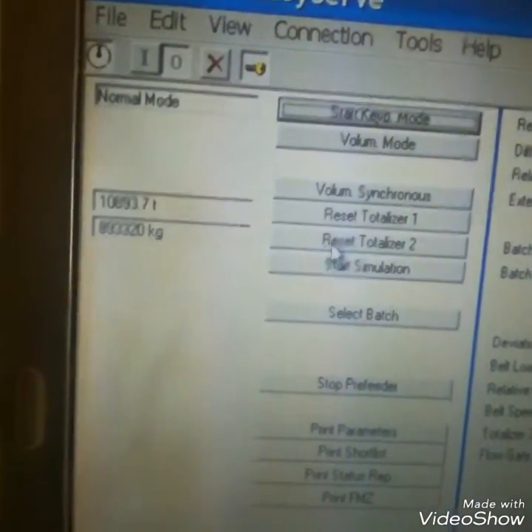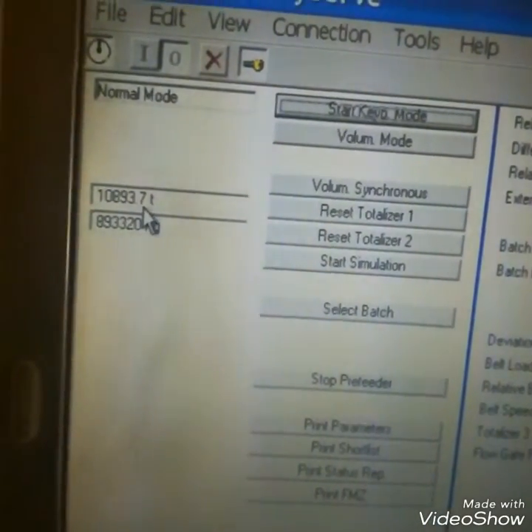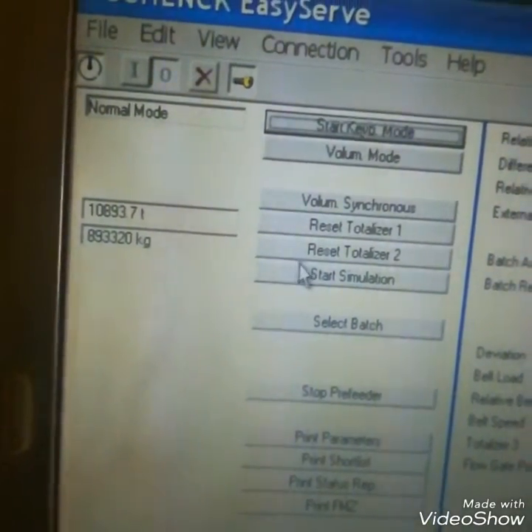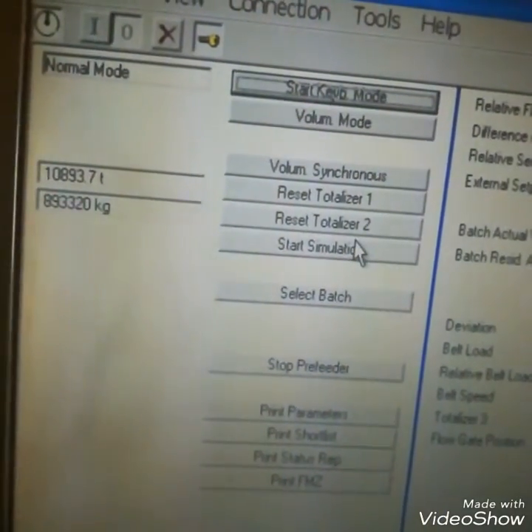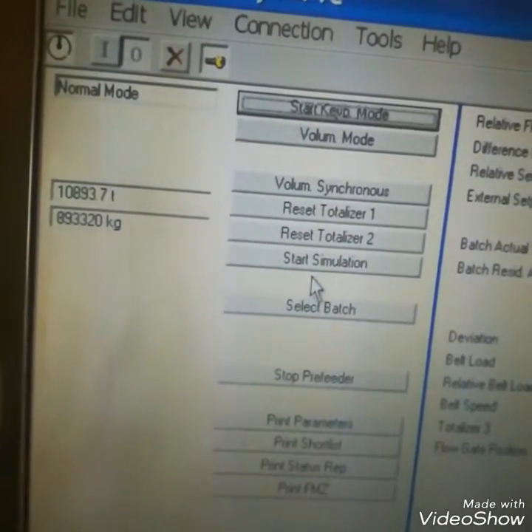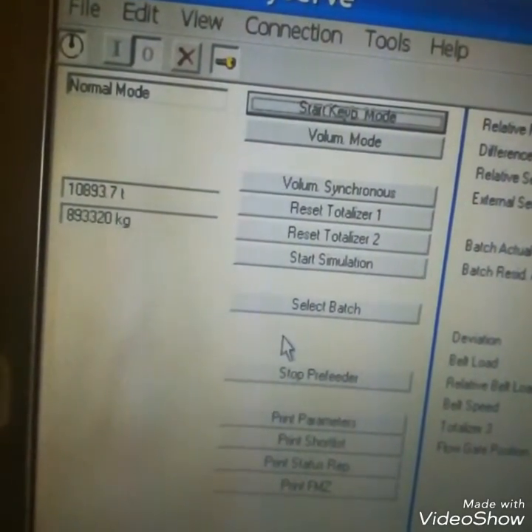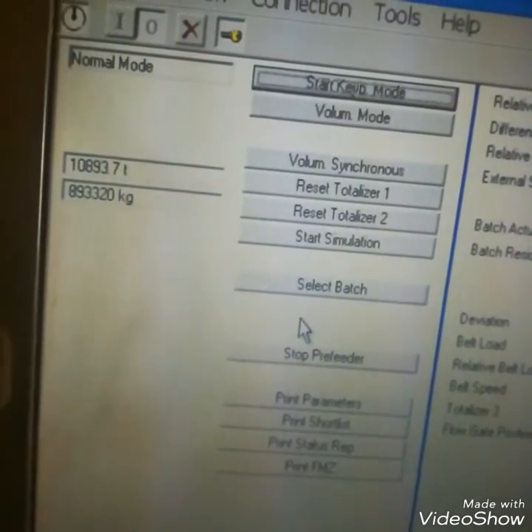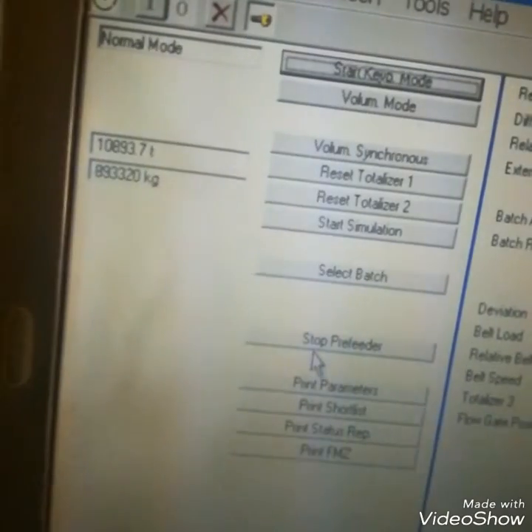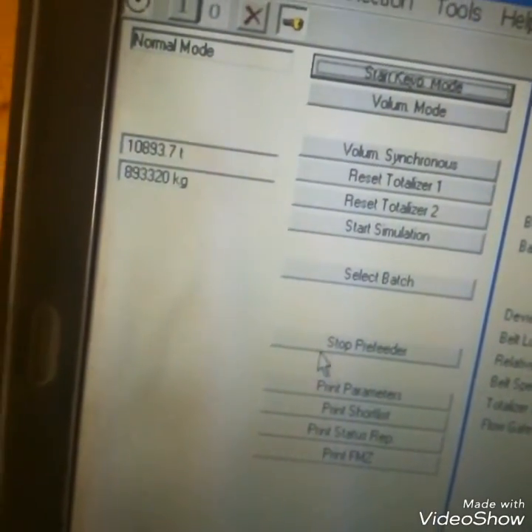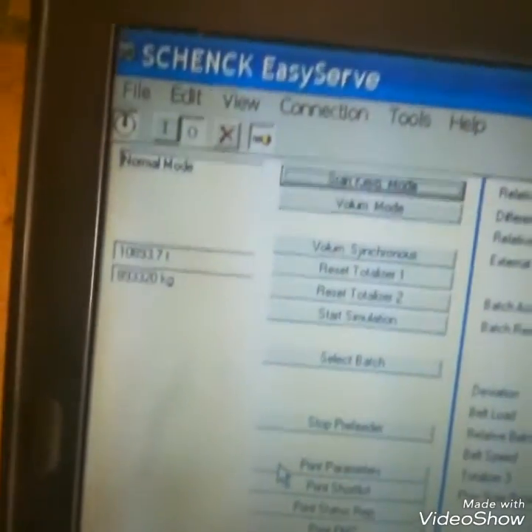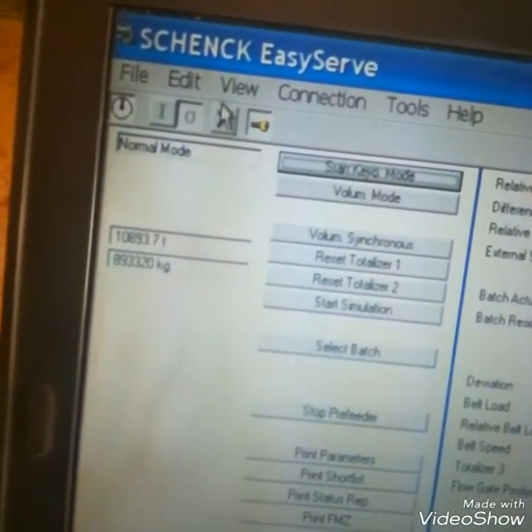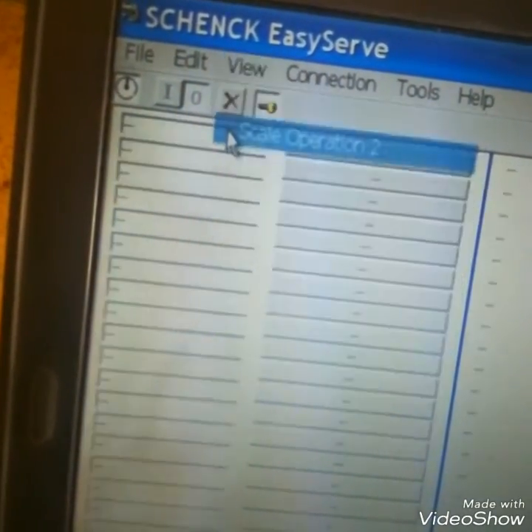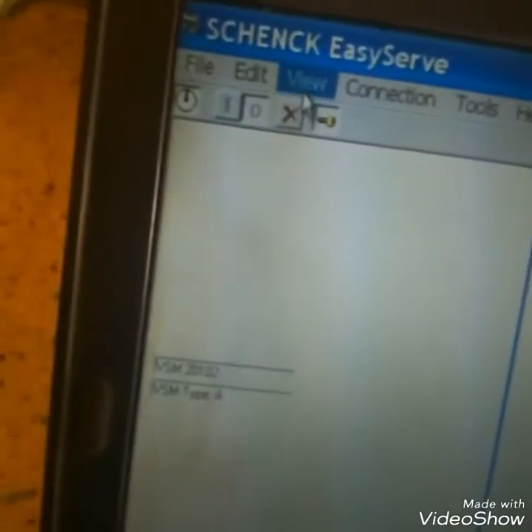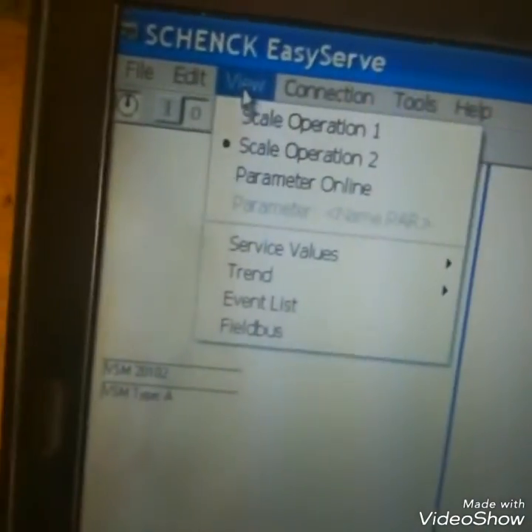Here you can see it's in the normal mode. There are the reset totalizer 1, reset totalizer 2, one is in tons and the other is in kg. So if you press this reset button, this totalizer will be reset to 0. Then there are two totalizers, one showing value in tons and the other in kgs. So you can see batch select. Batch is just, if you want a selected material, say 10 ton, then the weigh feeder will stop after giving 10 ton material. So this is called a batch mode.